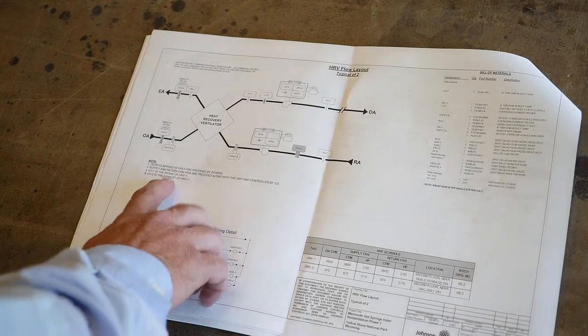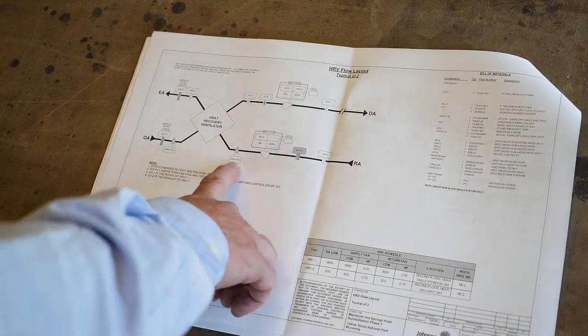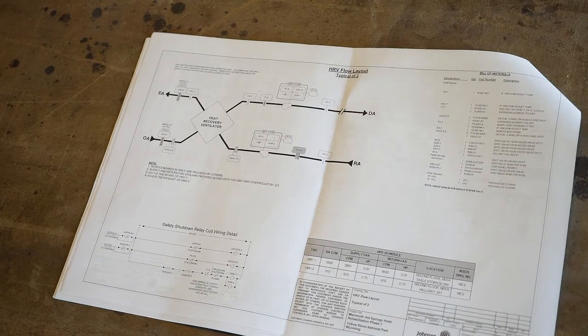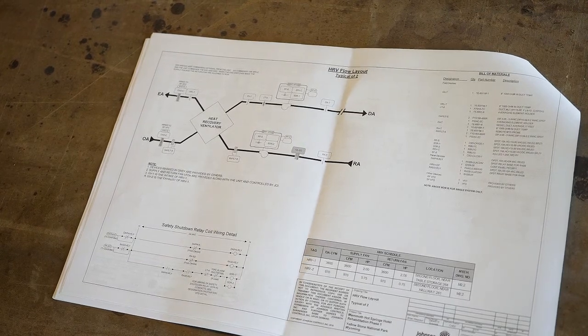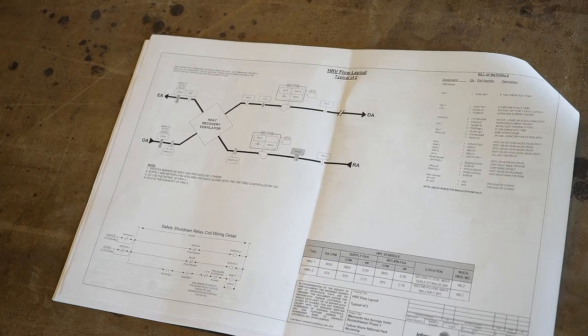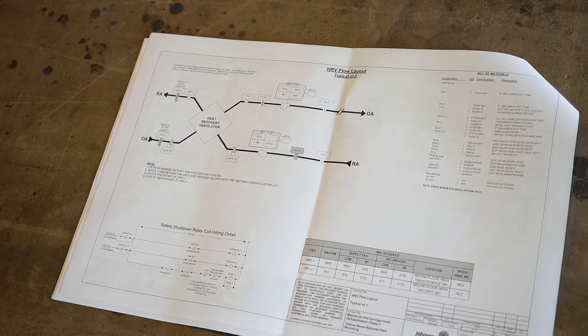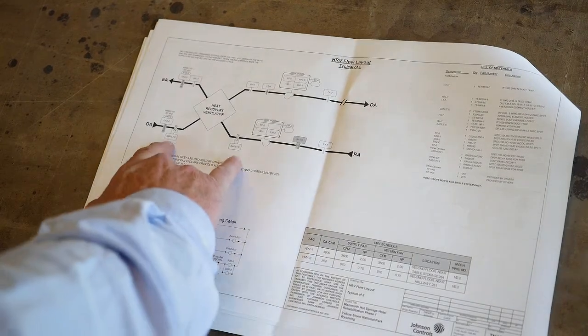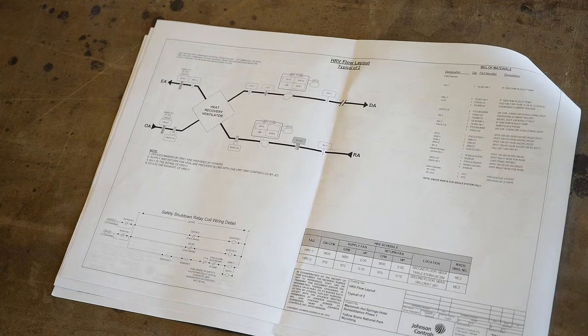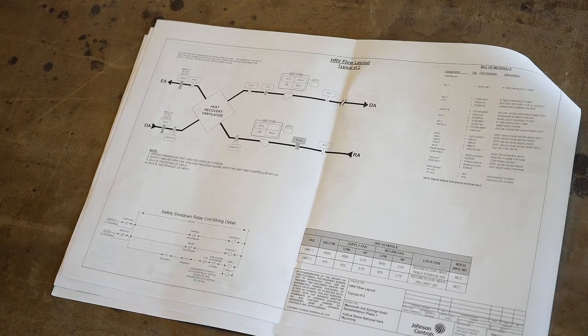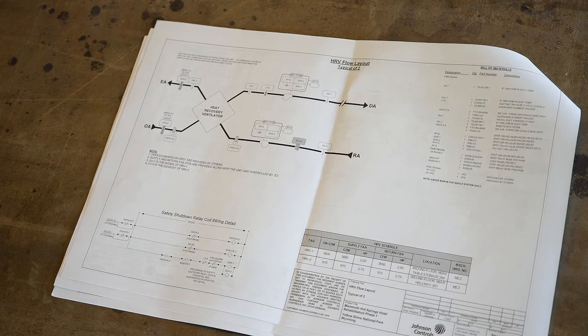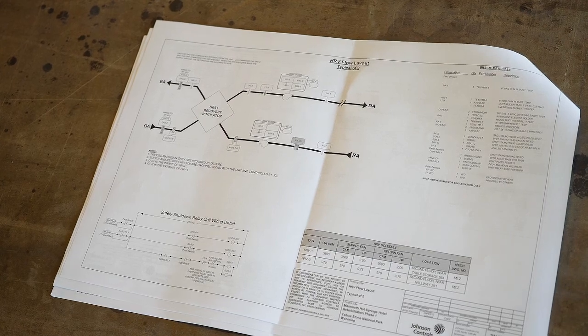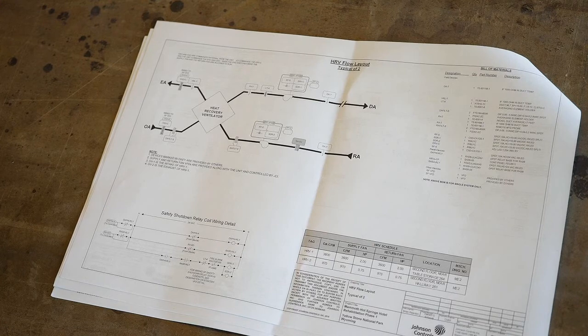Okay. We do have some outside air filter statuses, and we have a return air filter status. Those can be set so that if they get dirty, they trigger an alarm on the front end and remind you that it's time to clean the filters. And is that manometer based or just pressure differential? I've got to look at these. These look like they're just a switch. So when you get up there and you're ready to change the filters, if they're dirty, you'll need to adjust those with a screwdriver until they trip. Then the next time they get that dirty, based on differential pressure, it will trigger that alarm. How many sets of filters did you see in those HRVs today?